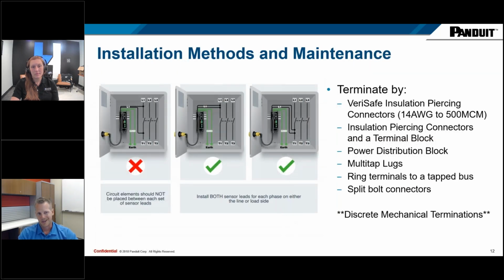Installation methods, how do you install this? Where does it go? Working left to right, you install this not spanning line and load, not spanning devices. Let me back up. When you're installing a VeriSafe, you've got the 6 sensor leads and 2 ground. You've got 2 leads per phase, so that's the 6, and then 2 for ground. So you've got 8 total sensor leads coming off of there.